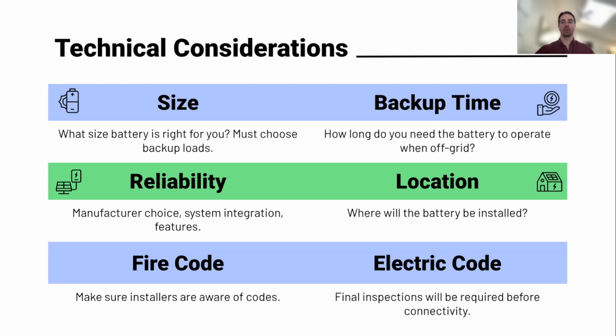Batteries installed inside do have to abide by a fire code. There are certain setback requirements and material requirements needed inside the home or room where the battery is installed. The room has to have fire-rated sheetrock in most cases, it has to have a hardwired smoke detector, and it can't be within a certain distance of different living areas. So there are certain considerations that need to be taken into account when these batteries are installed inside.